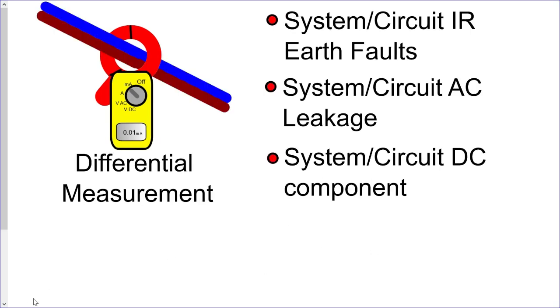For the purposes of the test moving forward, we're going to be looking at the differential method. Okay, can be used for system or circuit IR, insulation resistance earth faults, but generally we're going to be looking at system or circuit AC leakage, or the DC components that are getting inserted back into the RCD's toroidal core because of the electronic components that we've got connected downstream of the RCD.